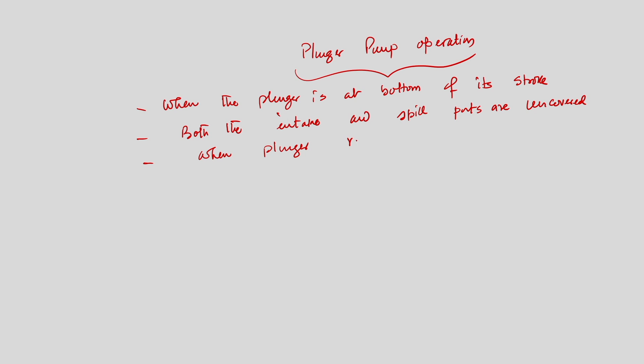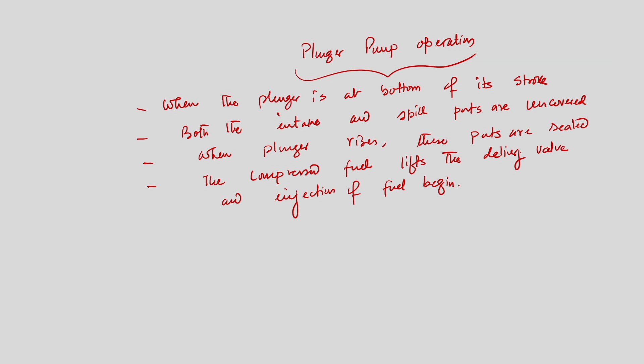The compressed fuel lifts the delivery valve and injection of fuel begins. Now, as the plunger continues to rise, the spill port is uncovered by the helical relief on the plunger.